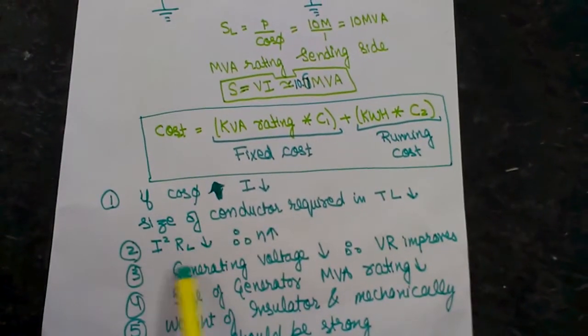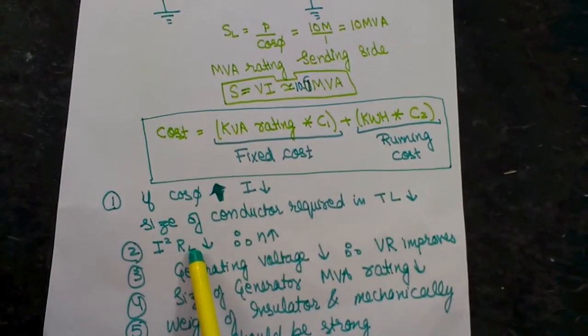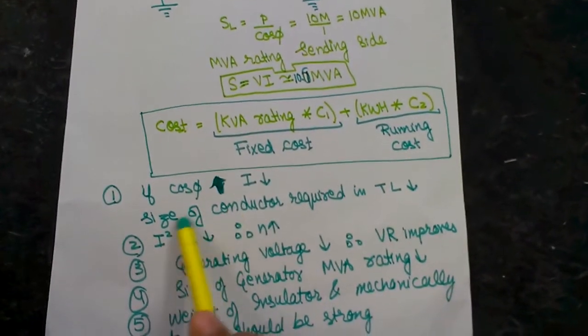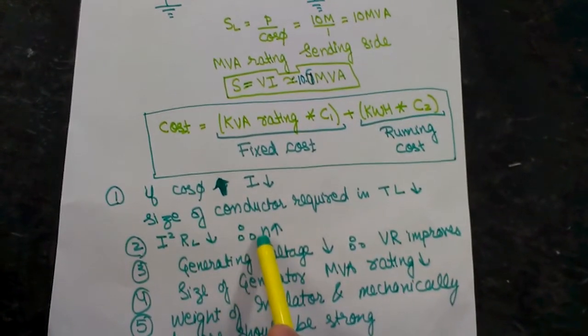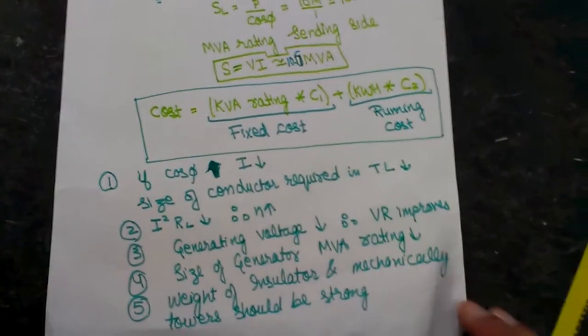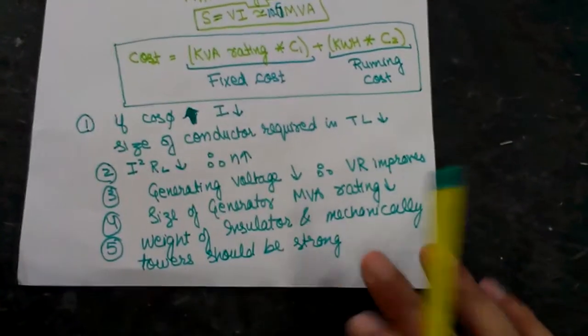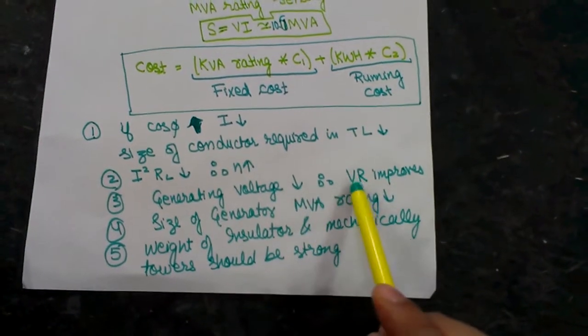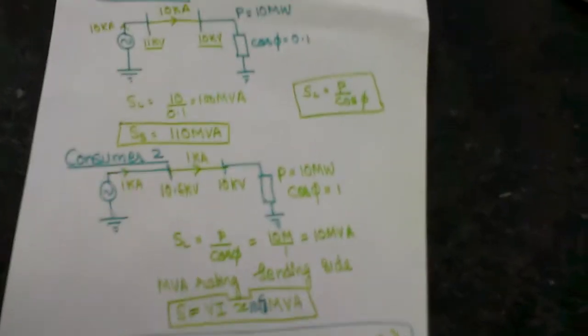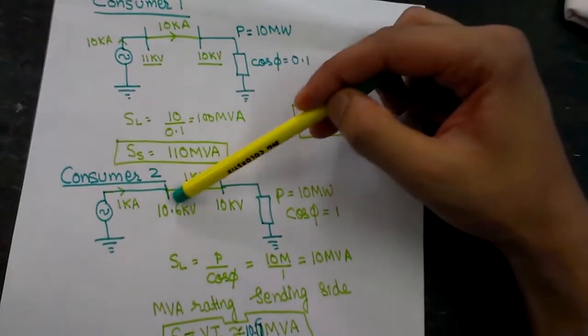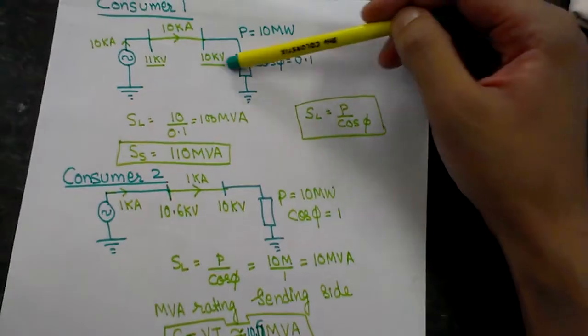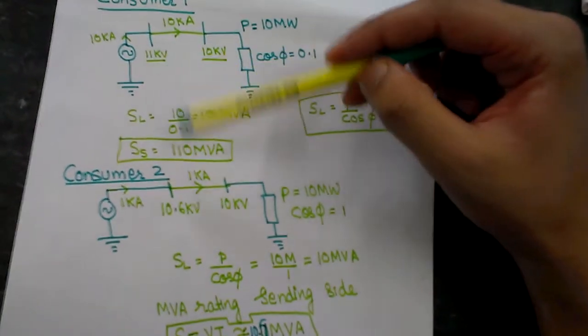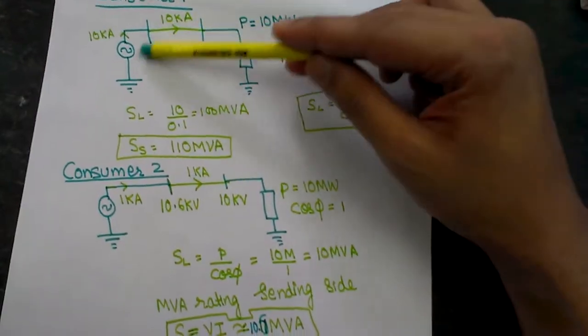As current increases, the I²R losses also increase. Conversely, if the power factor improves, I²R losses decrease and efficiency improves. Also, the generating voltage decreases, which means the voltage regulation improves. In the poor power factor case the utility had to generate 11 kV, whereas in the good power factor case they only had to generate 10.6 kV to deliver 10 kV to the customer. So voltage regulation improves and they have to generate less voltage.